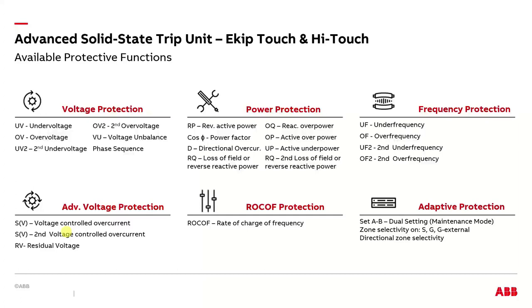Adaptive protection. You can set between two different setting groups depending on what you're doing, or, for example, I can do it automatically. So for example, you can have a setting group that allows a transformer to get through its inrush, so it's set a little bit higher. And then once two or three seconds go by, the breaker automatically will switch to a lower protective setting because it's already gotten past the inrush. So it gives you protection that can adapt on devices that are tricky, like a transformer, where you really, really would like to have it know what state the load is in. So that's a pretty interesting development.